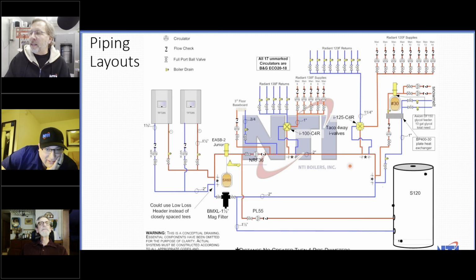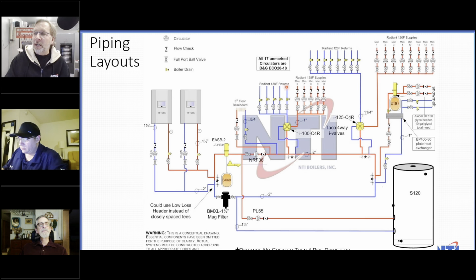Then coming off everything, every zone is on closely spaced T's. I did that because I wanted this pump to run all the time there's a heating call, and turn off when there's a domestic hot water call. So here we have baseboard, the hottest thing in the house, 3rd floor baseboard in this case, 180 degrees, coming off first. Second was a set of zones that needed 140 degree supplies going off to the radiant, to 5 zones of radiant through a mixing valve. That was a Taco i-valve, 1 inch. Then I used a 1.25 inch mixing valve for the 120 degree radiant zones, of which we had a bunch.